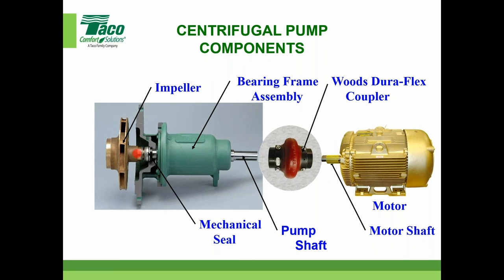So I always recommend the contractor buy a spare seal or two. Because during startup, unfortunately, these pumps are designed for clean water applications. And many times at the startup phase, it's not clean water, right?